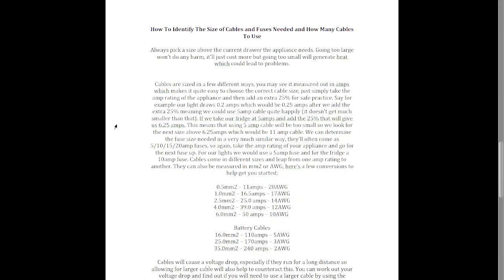I'm just going to quickly touch on how to identify the correct size cable and fuses needed in your electrical system. It's really important that you always pick a cable size above the current draw that the appliance needs. If you go too large, that isn't going to do any harm, it just costs a bit more money for the bigger cable. But if you go too small, that's when problems start, as it generates heat in the cable. For example, if you had a 10 amp appliance and used a 5 amp cable, that would generate a fair bit of heat and lead to problems.